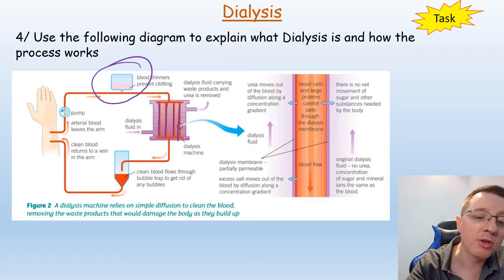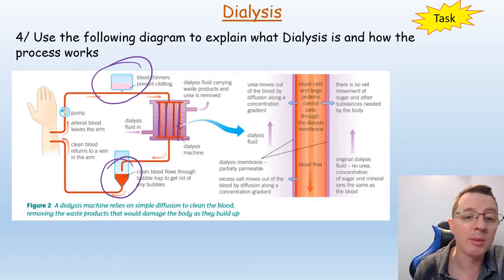And before the blood goes back into the person, it will go through a bubble trap to get rid of any bubbles, because if you end up with bubbles of air within your blood, it can kill you, and this is a very, very serious issue.